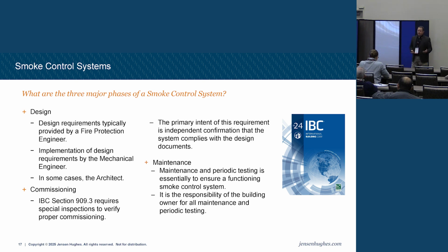If you've got maintenance contractors coming in, one big reason I mentioned earlier, I don't like the building automation systems interacting with my fire alarm systems and the smoke control. The biggest reason is that most technicians who work on big fire alarm systems understand that their job is life safety. Mechanical contractors may or may not. They may be really phenomenal at putting in air handlers, but they understand I've got to balance my system, I need this much airflow, I need this much temperature, I've got to run this much airflow to maintain that temperature. They're great at all that.